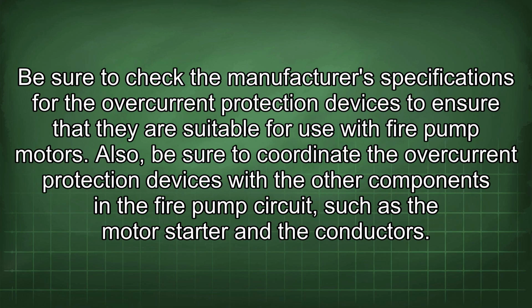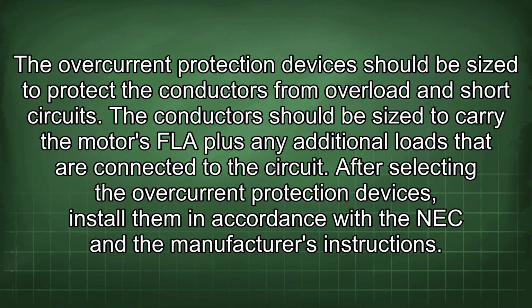Be sure to check the manufacturer's specifications for the overcurrent protection devices to ensure that they are suitable for use with fire pump motors. Also, be sure to coordinate the overcurrent protection devices with the other components in the fire pump circuit, such as the motor starter and the conductors. The overcurrent protection devices should be sized to protect the conductors from overload and short circuits. The conductors should be sized to carry the motor's FLA plus any additional loads that are connected to the circuit.